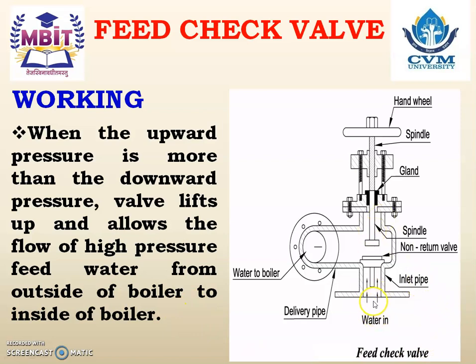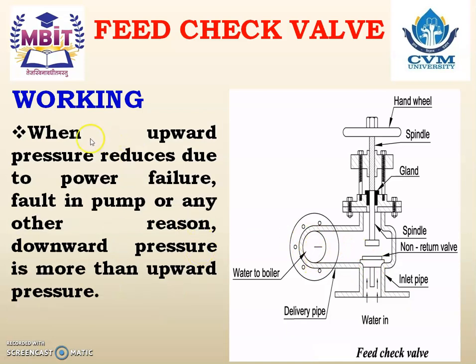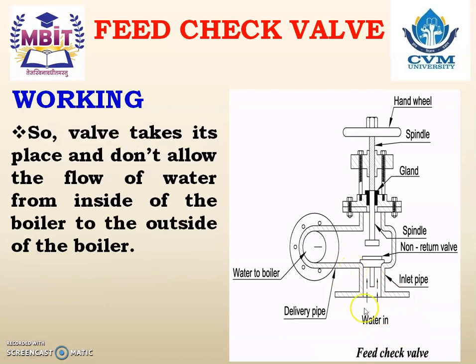If the pressure of feed water is high, the non-return valve will lift up and water will enter into the boiler. When upward pressure reduces due to power failure, fault in pump, or any other reason, the downward pressure becomes greater than the upward pressure. In that case, the valve takes its place and does not allow the flow of water from inside of the boiler to the outside of the boiler.